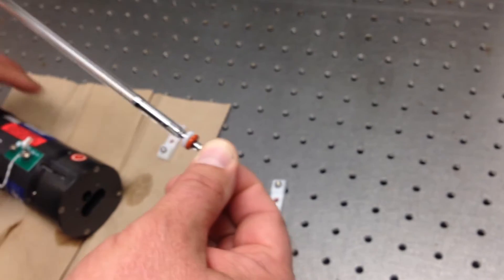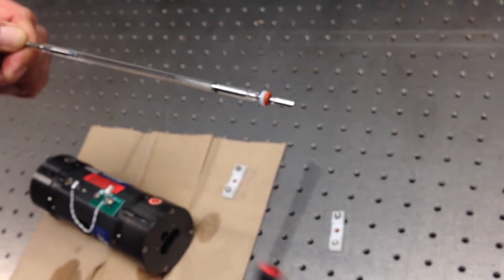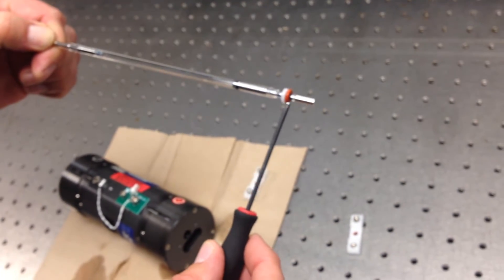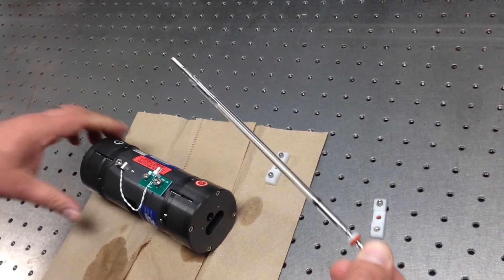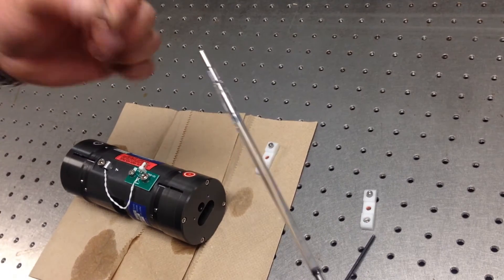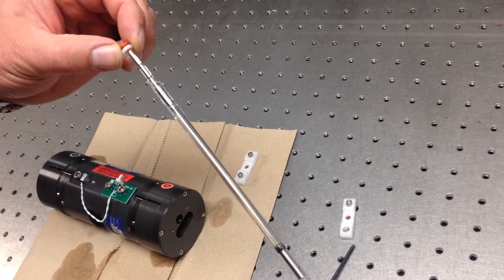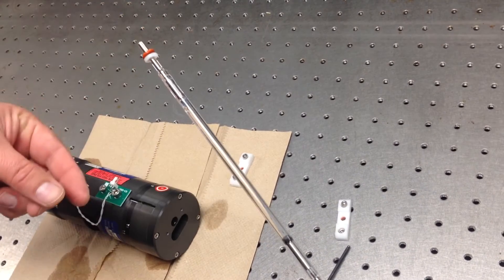Note that the flash lamp has a washer and an O-ring and that's on both sides. And just note that this one over here has fallen out. So it'll basically just slide on like that.